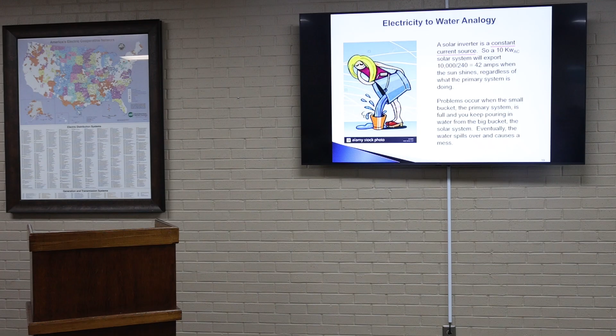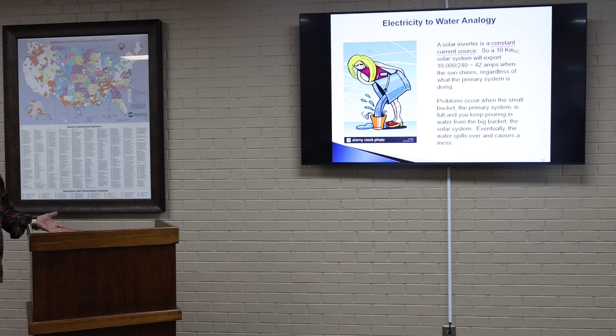So what do you do with it? Well, there's the trick. You have to figure out where it's going to flow, and if you can use it, or if it causes other problems before you can dissipate it. Too much would probably raise the voltage up. So we'd probably limit it, say you can install 13, but you can only export 10 onto the grid at any point in time, because that's all they can handle at that location, and each and every location is different.